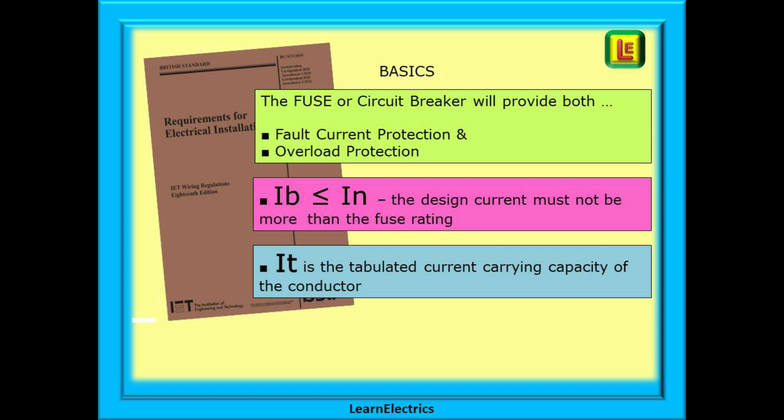IB, the designed current, must be known first, and it must not be more than IN, the fuse rating. Find IB and then choose IN. And IT is the tabulated current carrying capacity of the conductor, which we calculate once we know IN, the rating of the fuse or breaker.